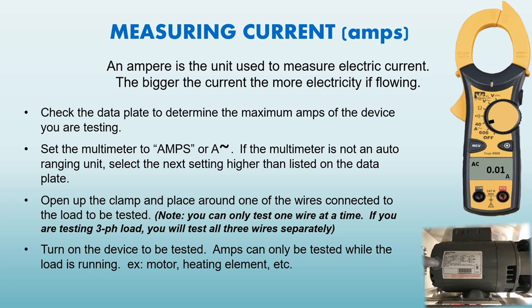Turn on the device to be tested. Amps can only be tested while the load is running or operating. For example, a motor has to be on, the heating element has to be heating up, and so on. The only way to test amperage is while a load is actually consuming current. Also keep in mind, when you're checking your amperage max load, once the amperage starts exceeding that, you're starting to have a couple of problems.